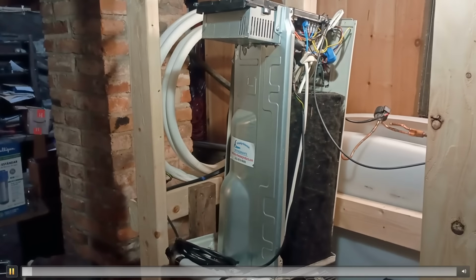So what I did was I modified this, and I installed a tank. So here's the tank here. I put that evaporator, or heat exchanger, into a tank, and then that liquid comes out of the tank and is pumped into the ground loops, and we'll get into this. I guess we'll hit this right now. Here we've got a temperature measurement. Here we've got a pressure measurement. It goes through this, and then comes back. Then we have a temperature measurement, and then we have a flow measurement, and then it goes back into the tank. So this is how this operates.